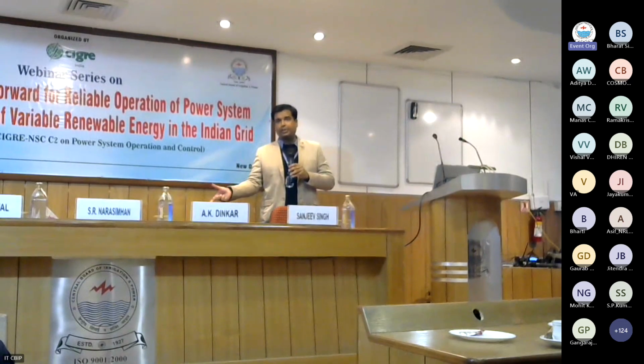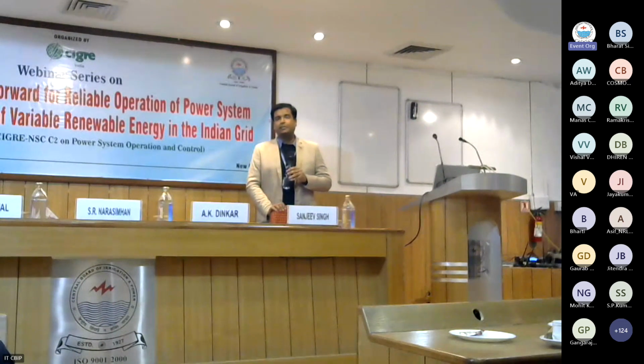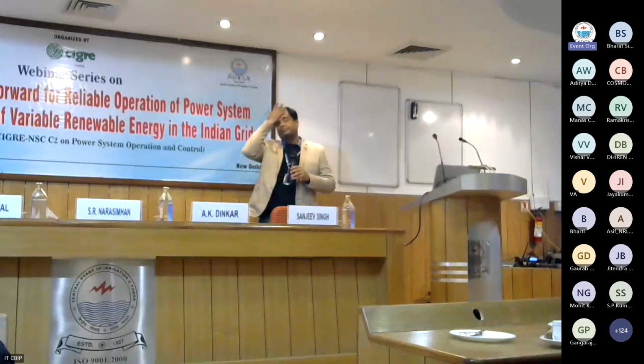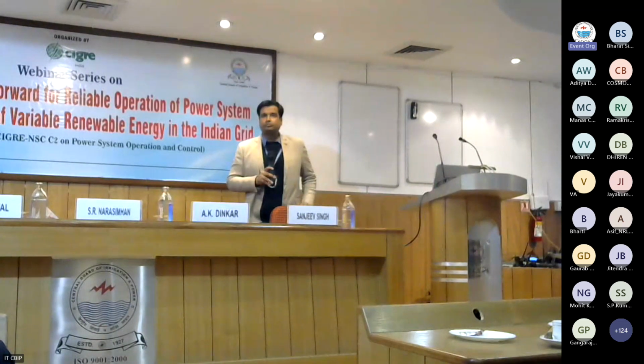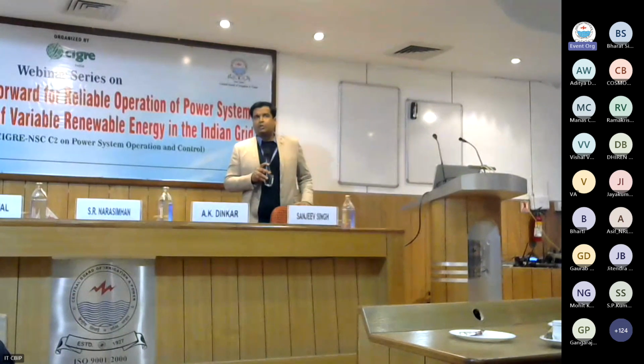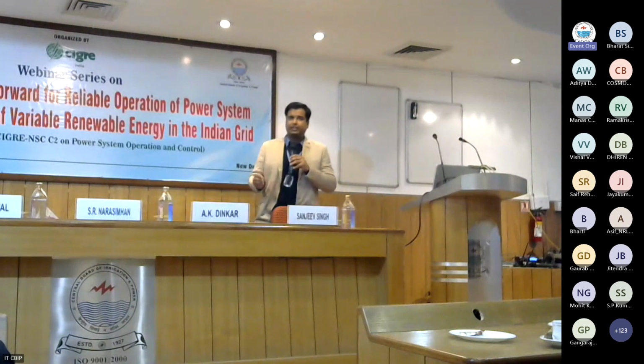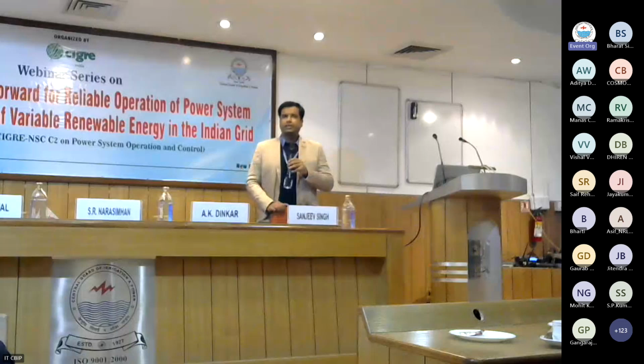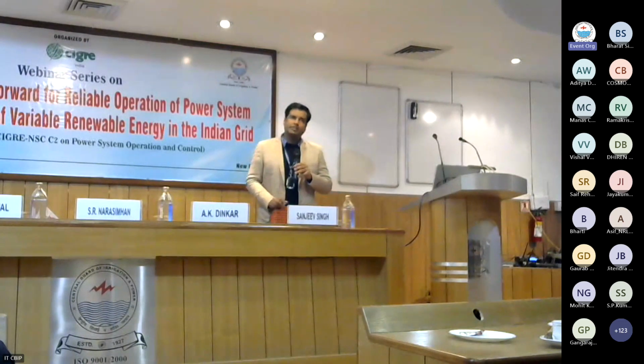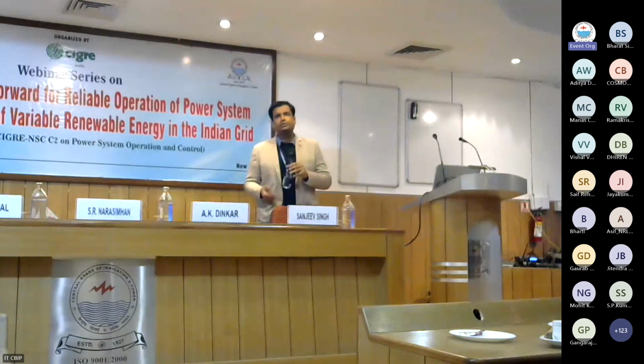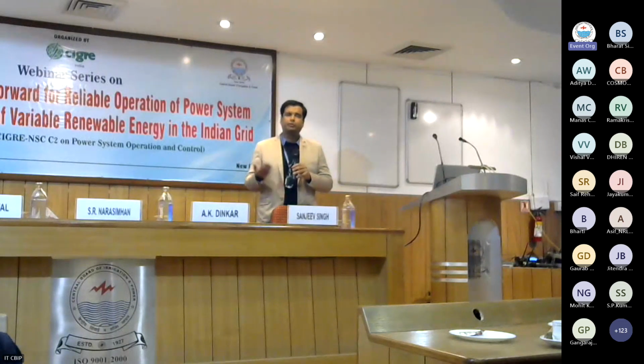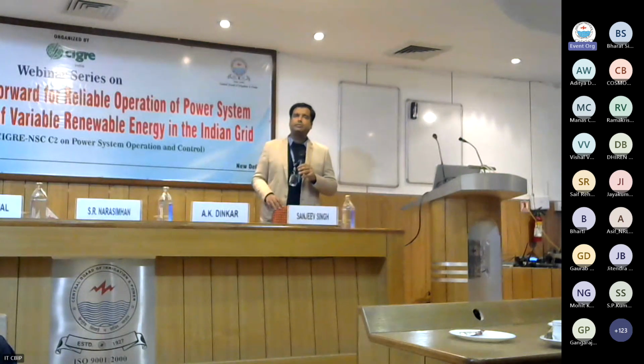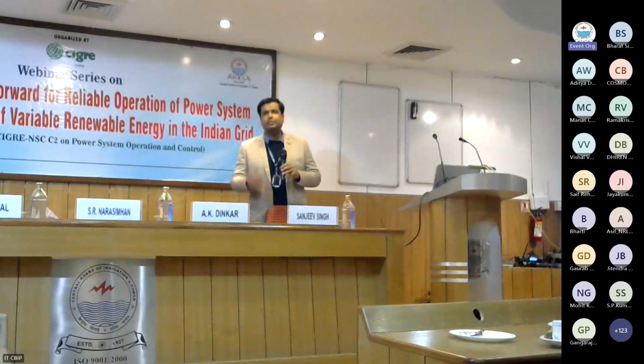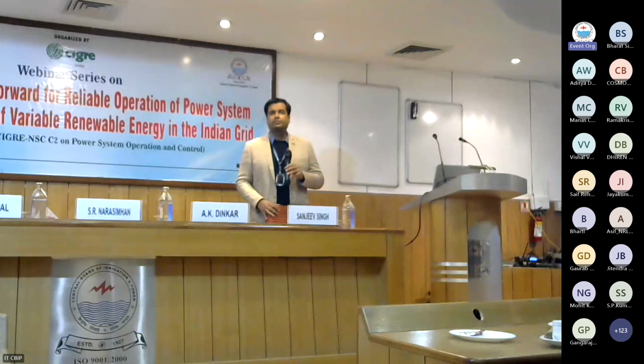Yeah, frequency dipped to 49.40 hertz, the level 1 of under frequency load shedding. And I think currently the CEA or BIS has no mandatory DFR included on the plants, right? Most solar plants have actually installed digital fault recorders. Plants have digital fault recorders on their dedicated transmission lines, the dedicated 220 kV lines. Within the plants, several inverters have an inbuilt feature also, but there are problems in sharing and archiving those details. They need not go for extra installation of equipment. Those features are available in the inverters and equipment of the RE plants, but there are some issues in the sharing and retention of that data.